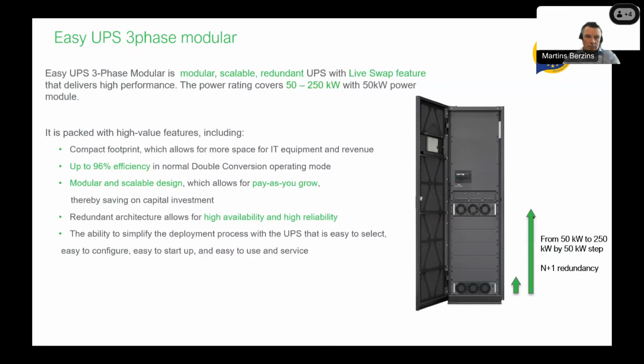Yes, so talking about the Easy UPS Modular. It's a highly modular, scalable, and redundant UPS with live swap features that can deliver power from 50 to 250 kilowatts in N+1 configuration. Here in the right corner, you see the initial frame of the UPS. By default it comes with a 50 kilowatt power module integrated. So from the beginning, it's a 50 kilowatt module.